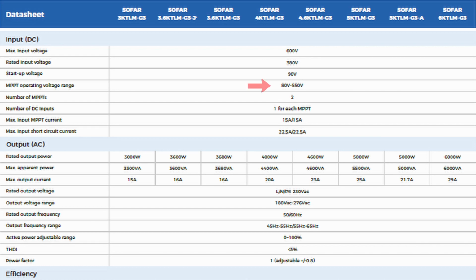Okay. MPPT operating voltage between 80 and 550. There are 2 MPPT trackers, one for each MPPT input. Maximum input current is 15 amps and maximum input short circuit current is 22.5. AC output maximum will be 6 kilowatts. Max apparent power will be 6000 volt amperes. Maximum output current up to 29 amps. Rated output voltage at 230. Output voltage range between 180 to 276, depends on the grid.